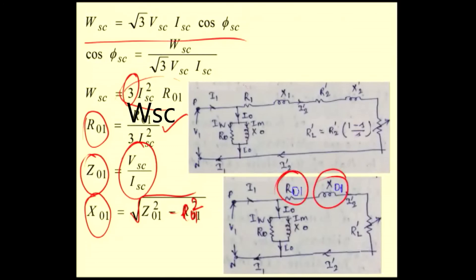By conducting the blocked rotor test, you are able to calculate R01 and X01. R01 is nothing but R1 plus R2 dash, and X01 is nothing but X1 plus X2 dash. Once you have these values — R01, X01, R0, and X0 — you can easily analyze the equivalent circuit.